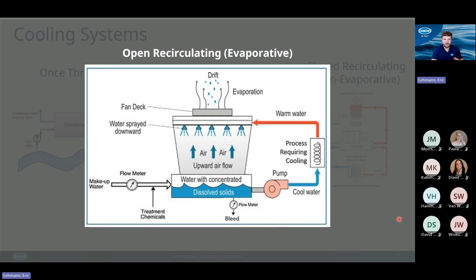Something that we need to discuss when we talk about this type of cooling tower is the cycles of concentration. So we saw in the previous slide how the water evaporates out the top. What happens there is, say we start off with, for example, just 5 liters of water. And as that water starts evaporating out, you lose the volume, but all the impurities become more concentrated in the solution itself. So if you evaporate out 4 liters, you're only left with 1 liter. You've concentrated that down to a 5x solution. So for example, if we're starting off at 20 milligrams per liter of, we'll just say hardness, after that 5th cycle of concentration, you've concentrated those impurities up to 100 parts per million. So that's what we consider cycles of concentration.